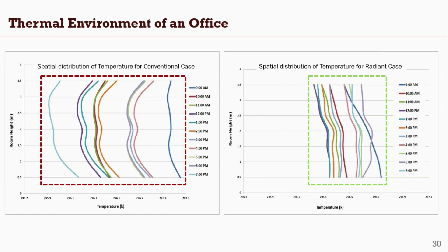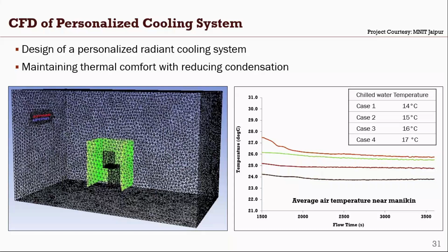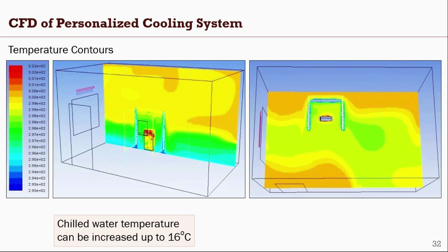Another case is a CFD of a personalized cooling system. You can see the design of a personalized radiant cooling system in which the person's cubicle has been fitted with radiant pipes and chilled water flows in the radiant pipes. Various cases were conducted, maintaining thermal comfort while reducing condensation. These are some temperature representations, and from the temperature representation and data, it was found that the chilled water temperature for this personalized radiant cooling system can be increased up to 16 degrees centigrade. In conventional cooling, it's around 7 to 8 degrees. So there is a lot of delta T, and thus savings can be achieved.